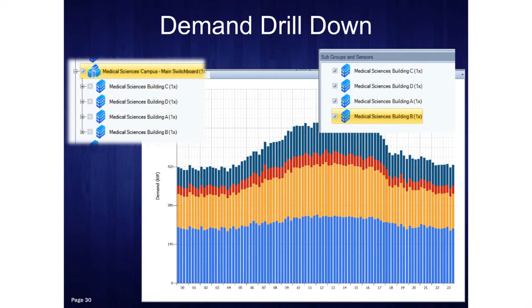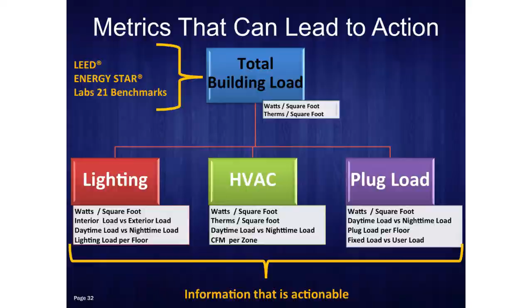Drill down on your demand then. So now I know what my total building is, I can start to drill down on that and really see which floor or which section of the building is using the energy. Baseline data, 1-minute, 15-minute data every day - I can set my min, my max, all these kinds of information. The nice part is that now I can start to set up metrics, to know whether or not I'm meeting the 50% reduction, to make sure I'm getting the payback on my investment, and that I can maintain that payback.